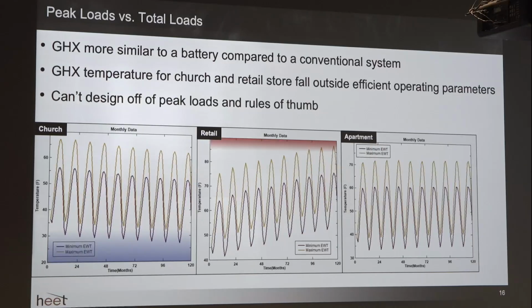But even in open loop systems, for example, where you're tapping into an aquifer and pulling heat and rejecting heat to an aquifer, we've been measuring a system in Winnipeg over the past 5 years or so, and they've increased the temperature of that aquifer by 5 to 8 degrees Fahrenheit, just because they're rejecting so much heat into that aquifer. So what can happen is this curve here, this temperature drift, where you may fall outside of those efficient operating parameters. When we talked about that ground source heat pump, it likes to be fed 30 to 90 degrees Fahrenheit water, right? But what can happen is you can fall outside of those efficient operating ranges if you're not considering your total loads, if you're only looking at your peak loads. So it's important to not only design, again, off of your peak loads, which are certainly important, but your total loads are also important to determine your total demand to design your supply.